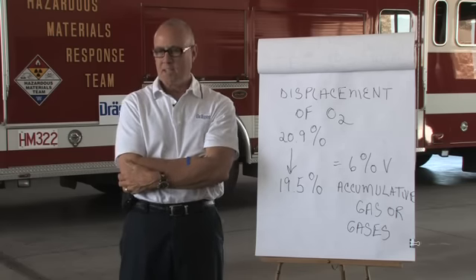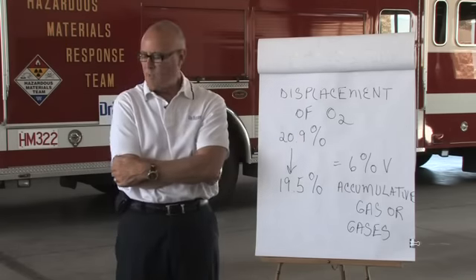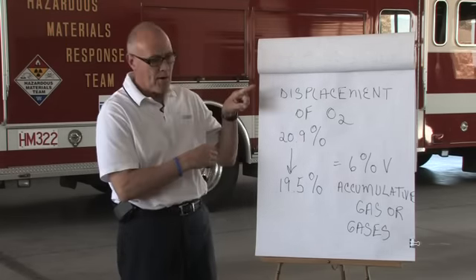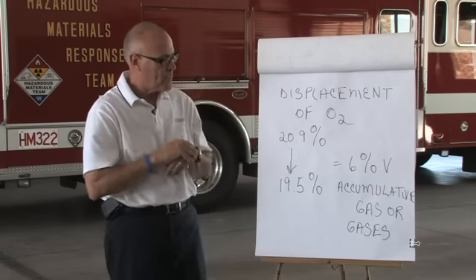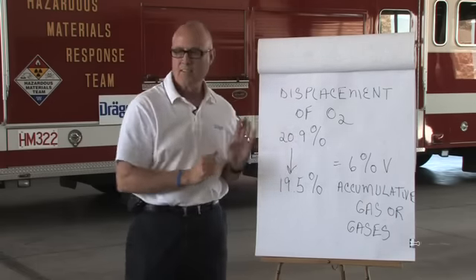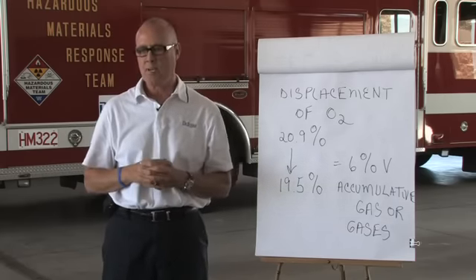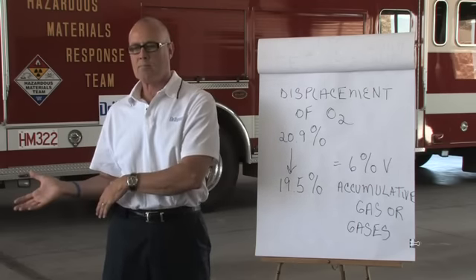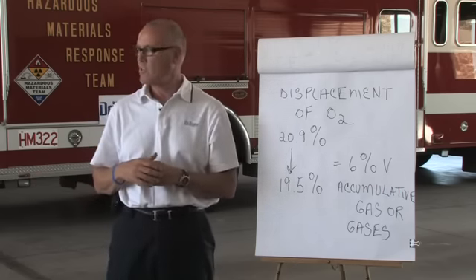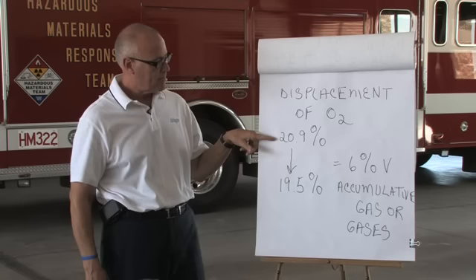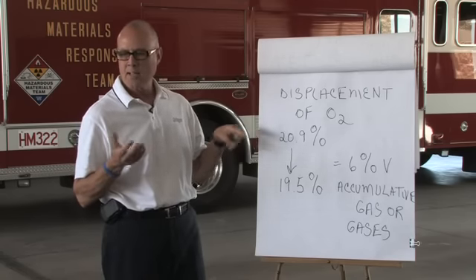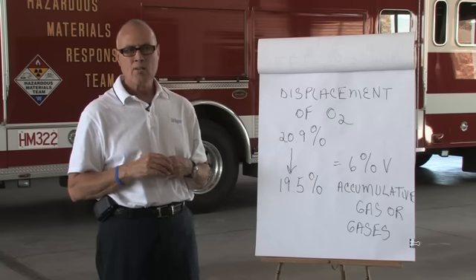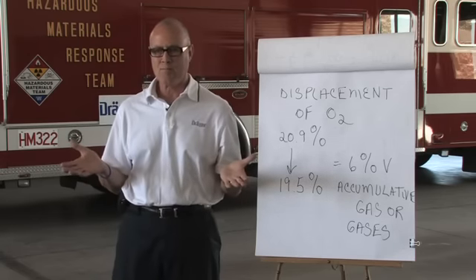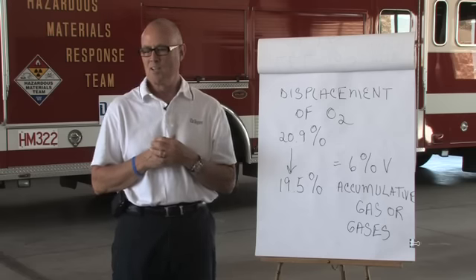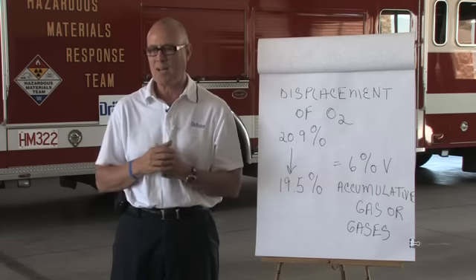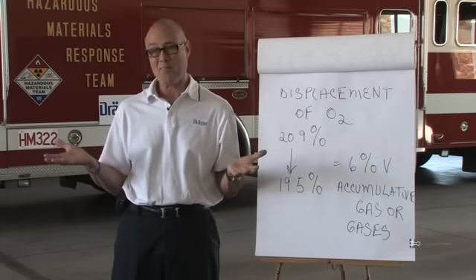Okay? And the same with oxygen. If you're not reading at 20.9, what that's going to have to do is, if you've got your 0 on LEL, your 0 CO, 0 H2S, but your oxygen's reading 20.6, it's going to prompt you to have to perform a fresh air calibration after your warm-up. Okay? And once you do that, you make sure you're in fresh air, and this will then come back up to 20.9 as your start point. Okay? Now, could you be in an environment that is suspect oxygen, where it went to 20.6? Could you really be 0.3% below on oxygen? If you're standing outside, the answer is probably no.